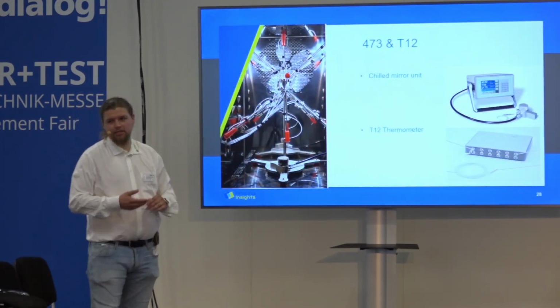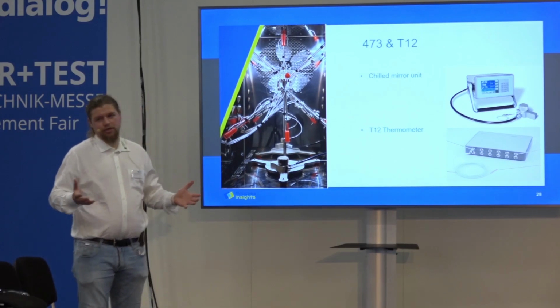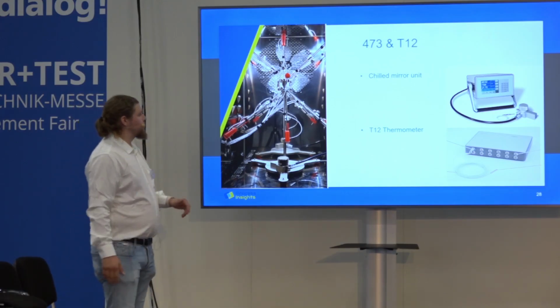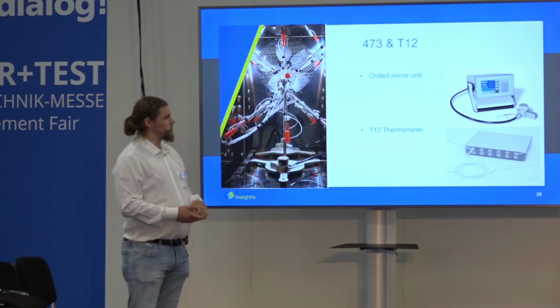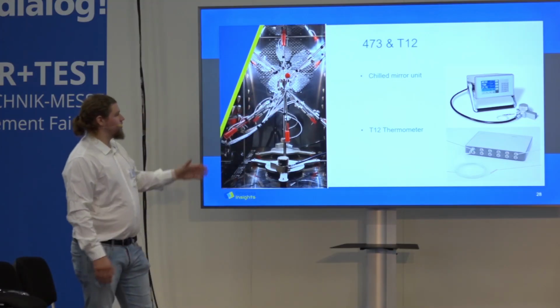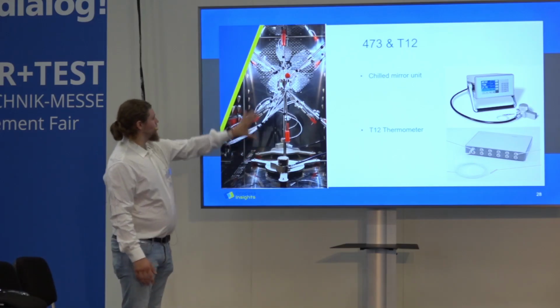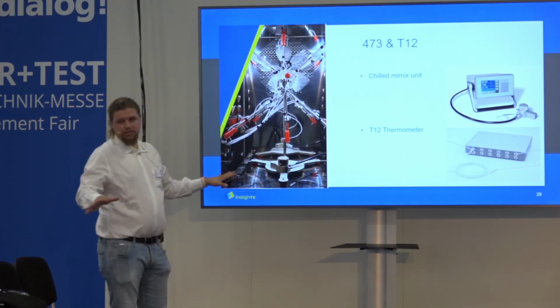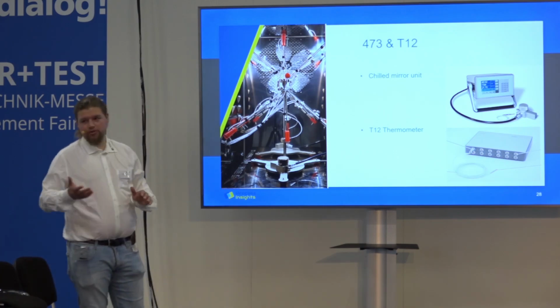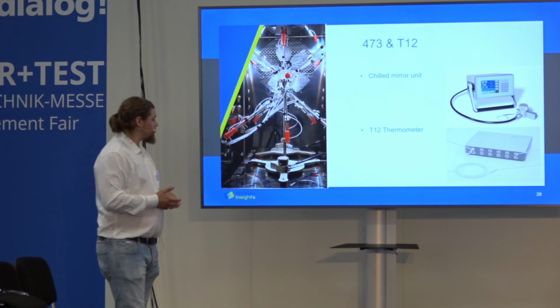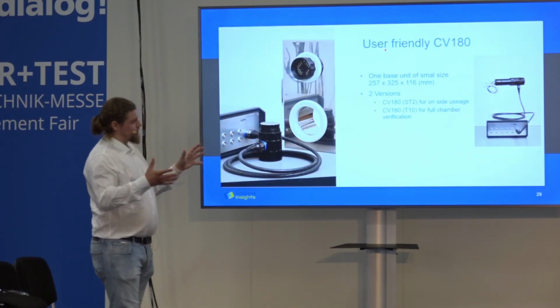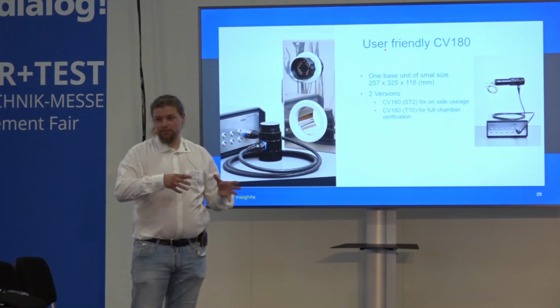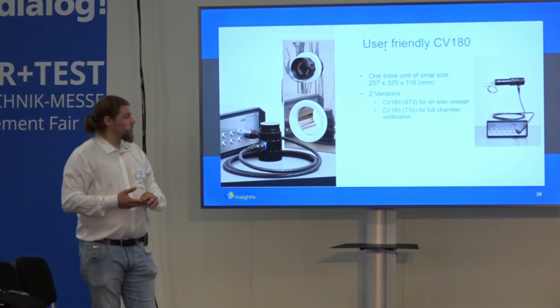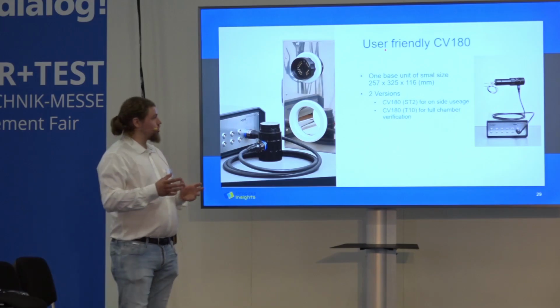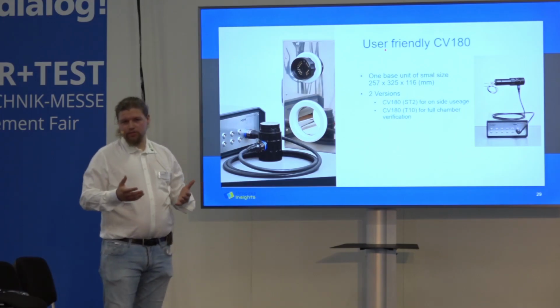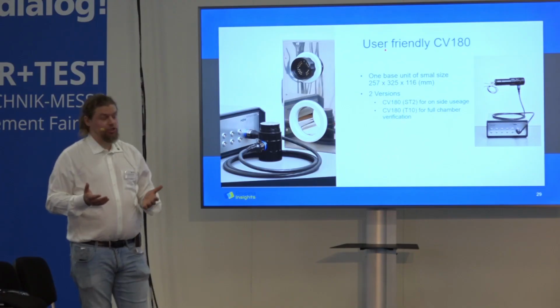So how were climatic chambers calibrated until now? What was the available equipment for that? Usually the chilled mirror was used, as we have here, a 473 SHX. And then you needed the temperature probes, so that you could spread them across the useful volume in your climate chamber, which will then be represented by your measurement. So in the past there was a lot of equipment, and the measuring head was placed inside the useful volume, which also caused thermal loads and effects on the measurement results.